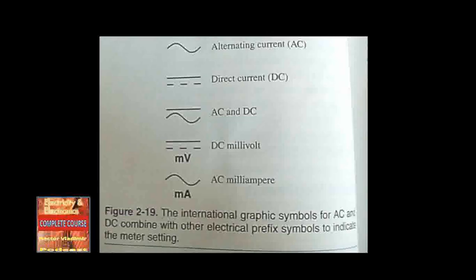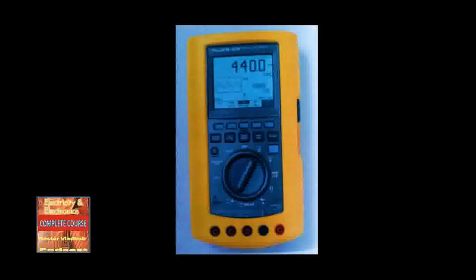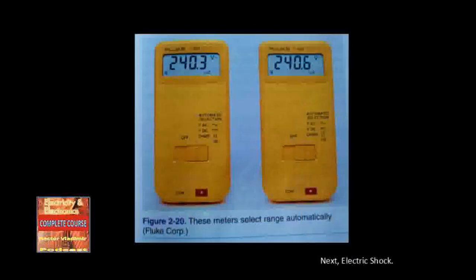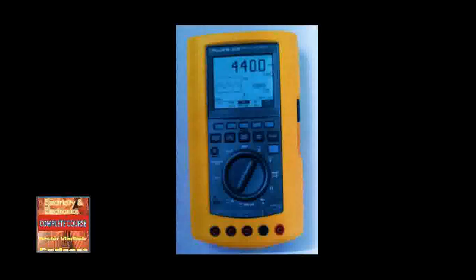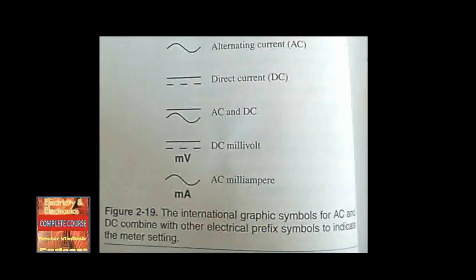Most digital meters use international standard labels to indicate various meter functions, such as AC and DC symbols combined with metric prefixes to identify the function or range of a meter setting. Many DMMs are equipped with protective circuitry to prevent accidental damage when the wrong function is used. Polarity is usually not an issue with digital meters — the meter will automatically adjust and flash a message on the LCD warning the user. Some digital meters have an auto-range feature that automatically selects the range through internal electronic circuitry. Resistance reading using a DMM still requires disconnecting the circuit from the power source to prevent damage.